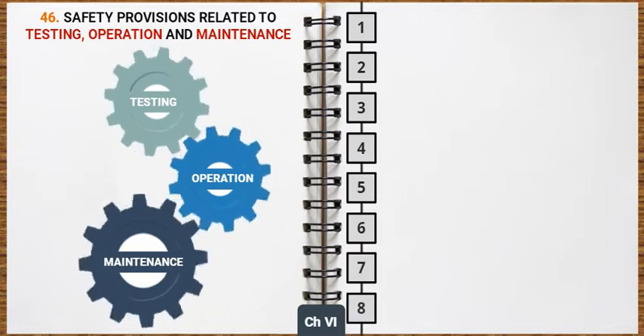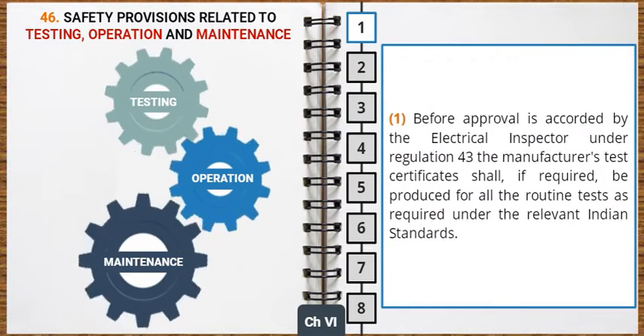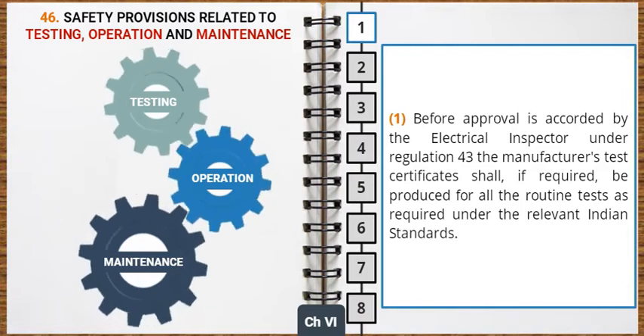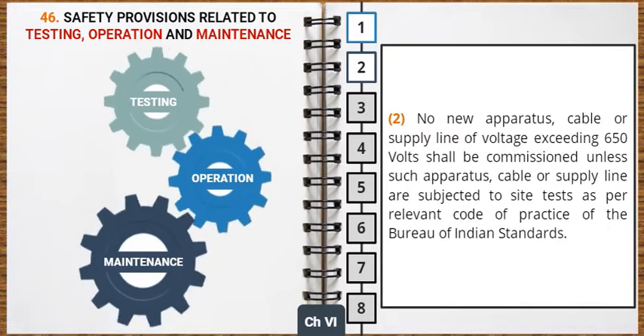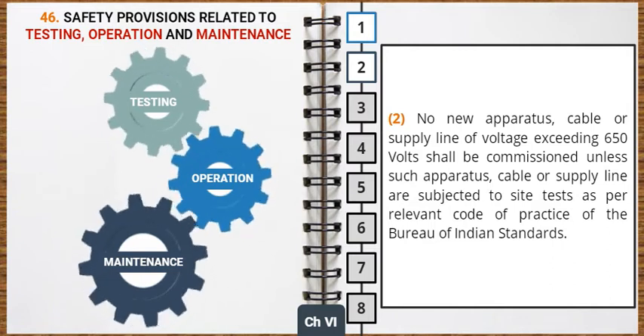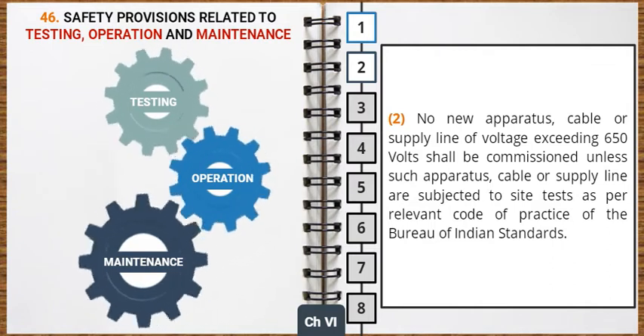Now, let us learn about the safety provisions related to testing, operation and maintenance. Before approval is accorded by the Electrical Inspector under Regulation 43, the manufacturer's test certificates shall, if required, be produced for all the routine tests as required under the relevant Indian standards. No new apparatus, cable or supply line of voltage exceeding 650 volts shall be commissioned unless such apparatus, cable or supply line are subjected to site tests as per relevant code of practice of the Bureau of Indian Standards.